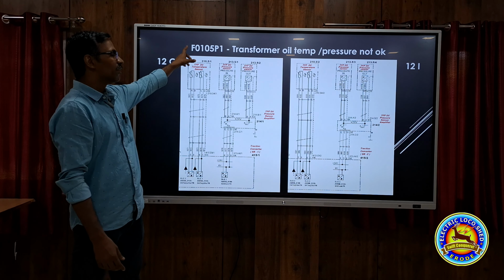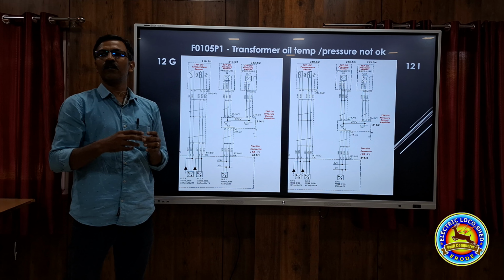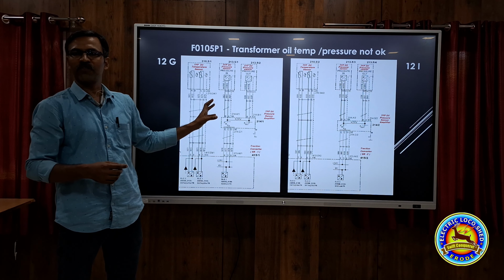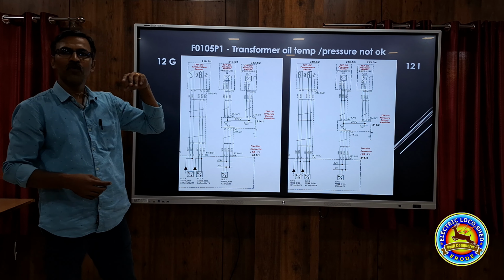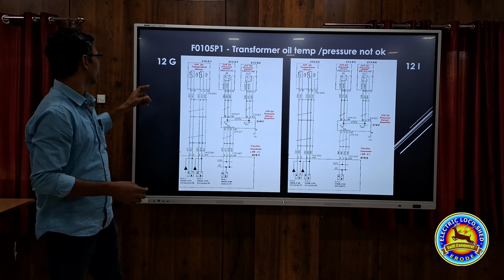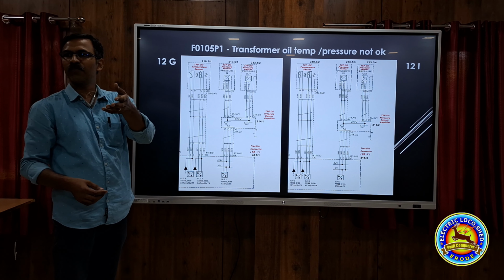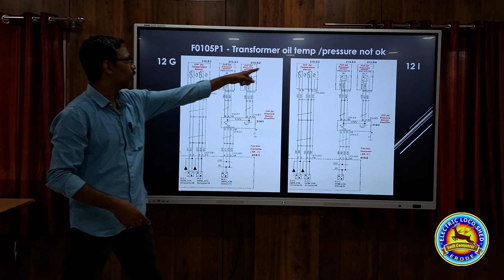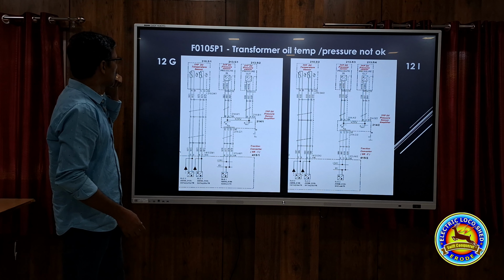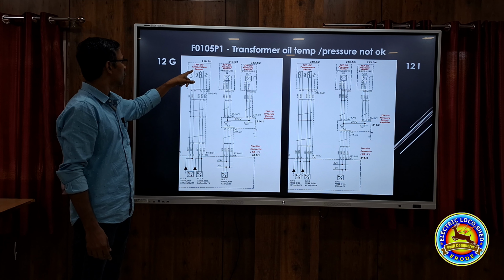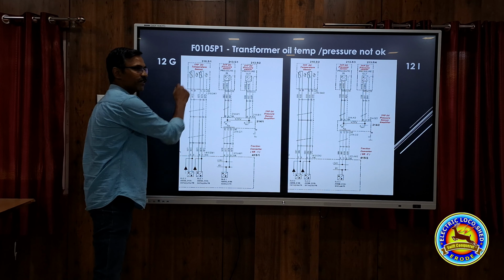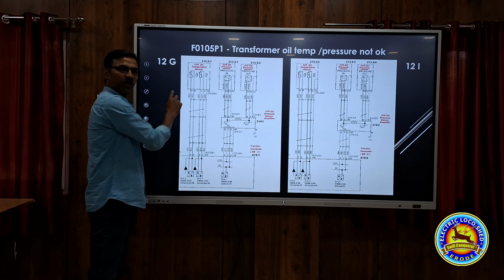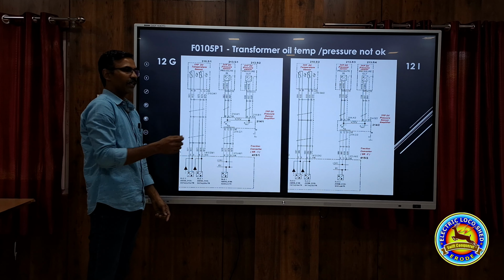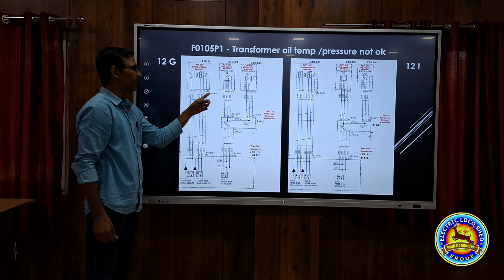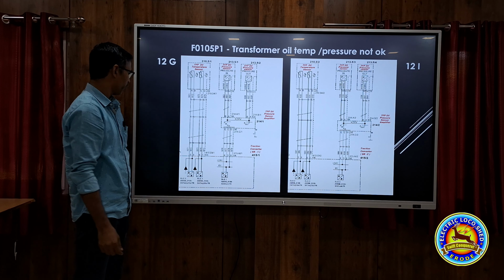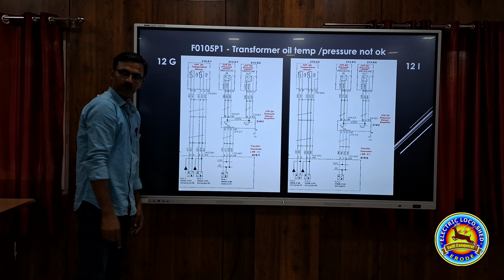What problem will we face in the loco because of malfunctioning of the sensors? So we should know where these sensors are connected. This is the 12G page of our three-phase loco circuit. This is the 12I page. In the 12G page, we can see one transformer oil temperature sensor. In that, 2 elements are there. One element is at AB, and the second element at CD. E port is the earth point, and it is connected to SR.